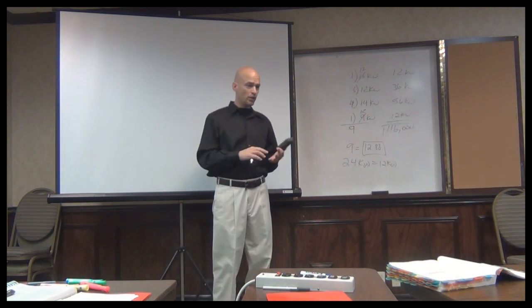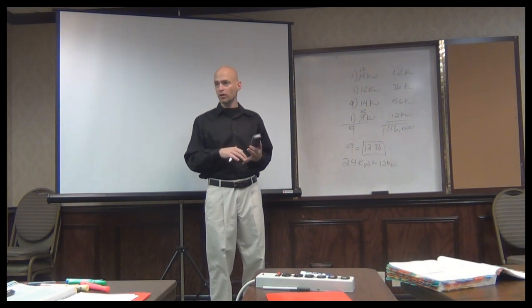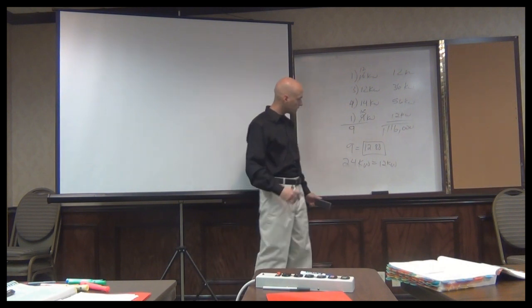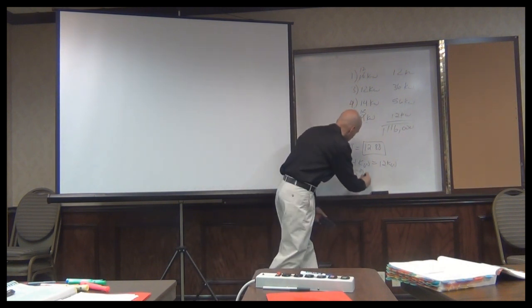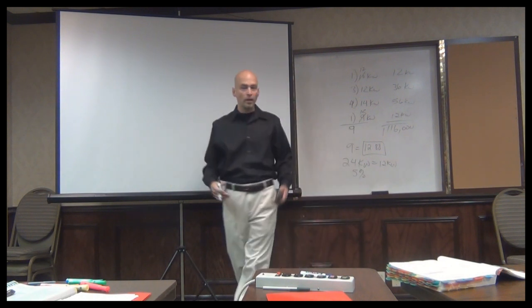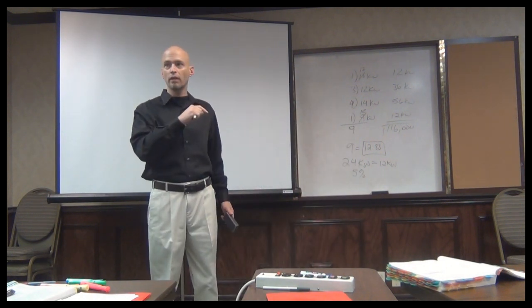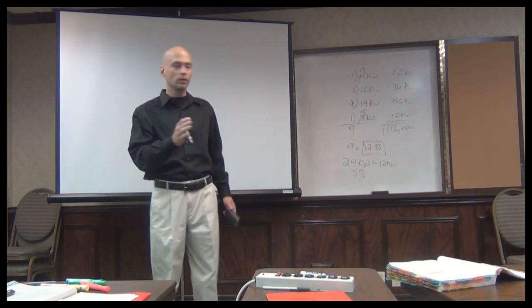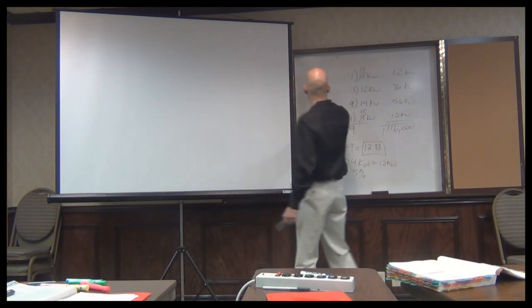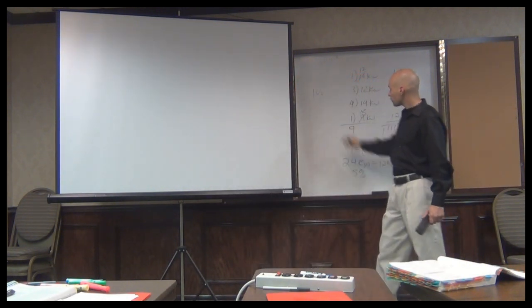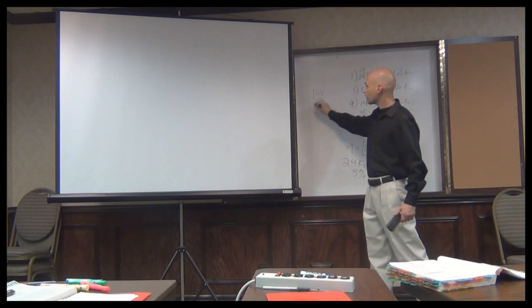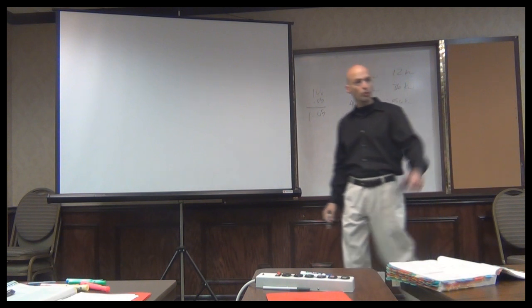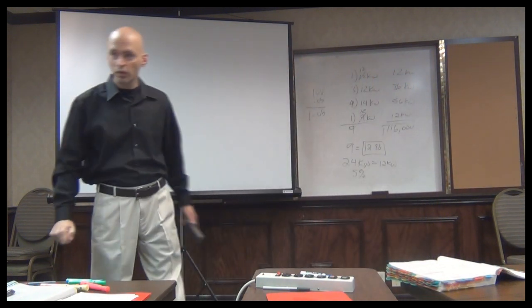It's really a reference to note 2 and then going back to reference to note 1 as well, because you have to increase that demand load. So that 24 kilowatts actually has to be bumped up by 5%. And when you're multiplying percents like that, just put a 1 in front of it. So you do 1.05 in your calculator, and that gives you 100% of the original number here plus the percentage, which in this case is 5%. So if you put in your calculator 1.05, 24 times 1.05 is 25.2.